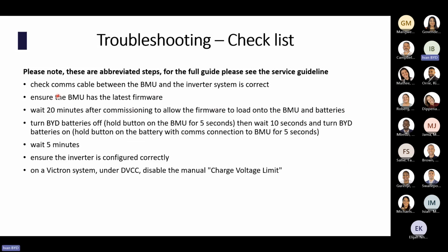Okay. If you can check the comms cable between the BMU and the inverter is correct, and then ensure the BMU has got the latest software, latest firmware. And then it's best to wait about 15 to 20 minutes after commissioning to allow the firmware to load onto the BMU and the batteries. That's just a troubleshooting checklist that we're going through. Then you turn the batteries off, then turn the batteries back on, wait 5 minutes, and that's a good troubleshooting process to make sure that everything's sort of been done.